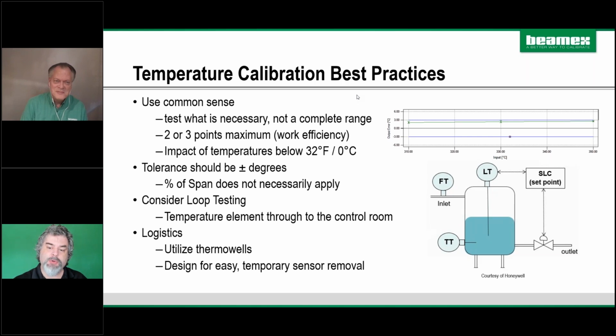One thing I wanted to mention is your example here. The transmitter, let's say, was 0 to 500 degrees, and we get this question a lot: what test points do I calibrate? Your example here is the process is right around 330 degrees, and you have 3 points from 310 to 350. This is a perfect example of calibrating what's important to you. If you had to find a temperature source that would work from 0 to 500 degrees, that would be extremely difficult, and you don't need that. If you have this, you can calibrate what's appropriate for your test and your process. I just wanted to point that out.